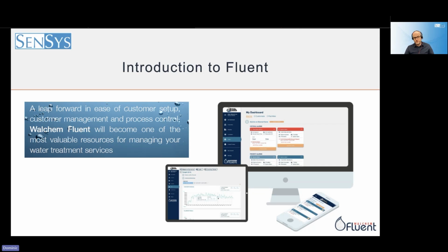So that opens up the possibility to hardwire this onto a site Ethernet system via their network. You can plug in your controller to that, ask them to set up some ports, which are part of the Fluent protocol, which we can send out what ports they need to do. Sites are more likely to allow these protocols, these ports to be opened because you're only sending data out, unlike the previous where you'd have to have a log into their system. Now you just have ports that allow the controller to log out.